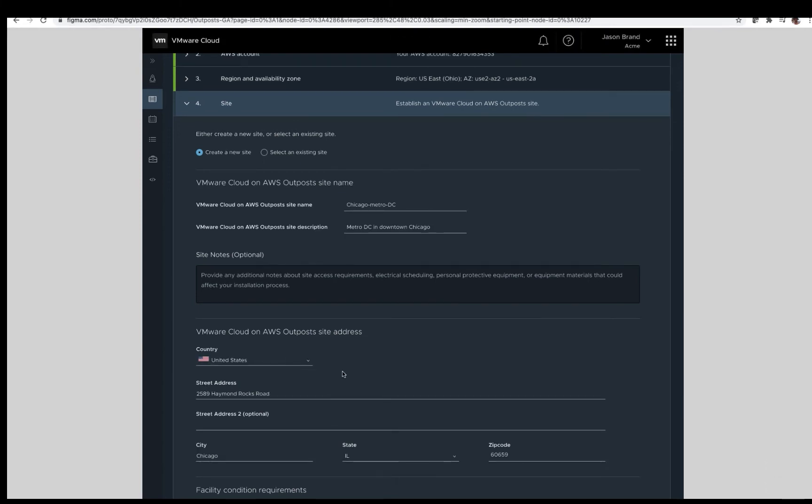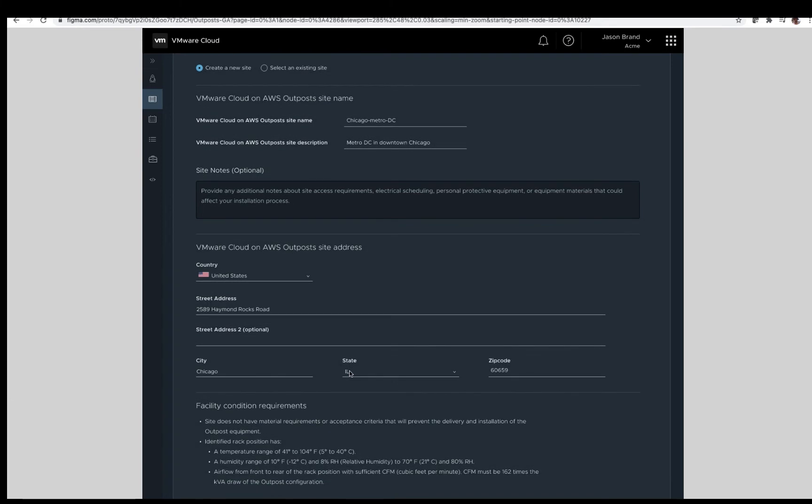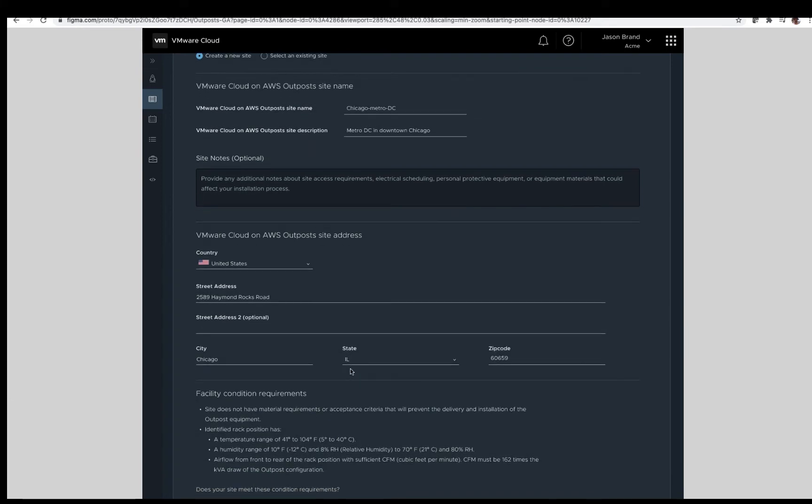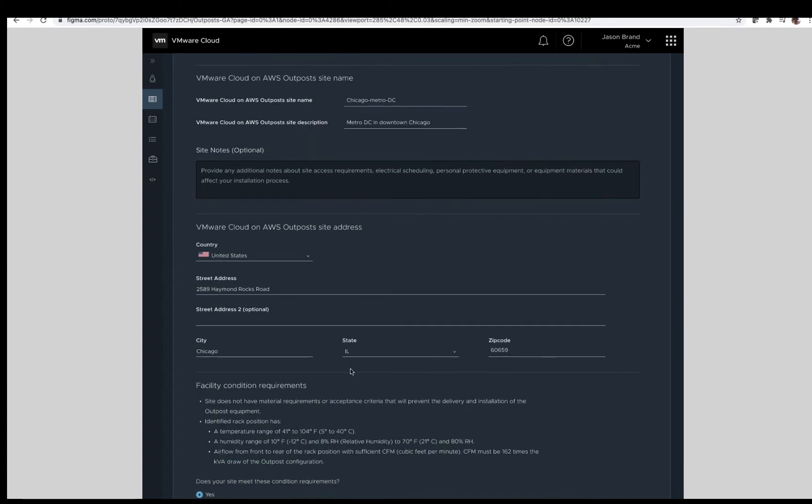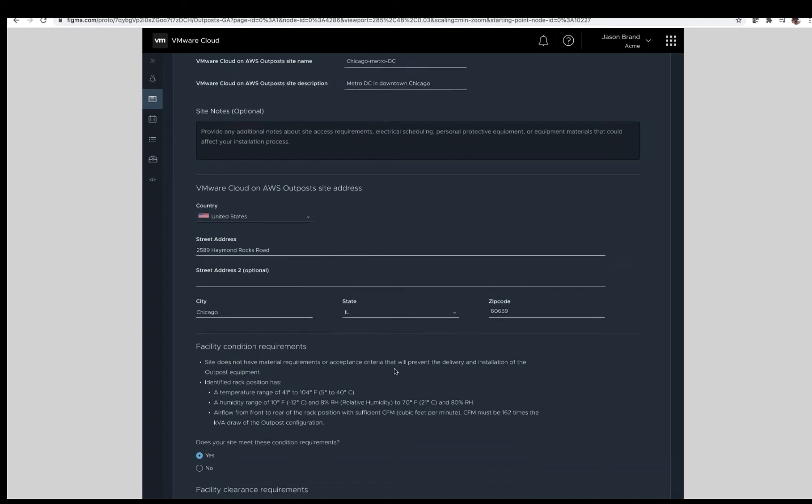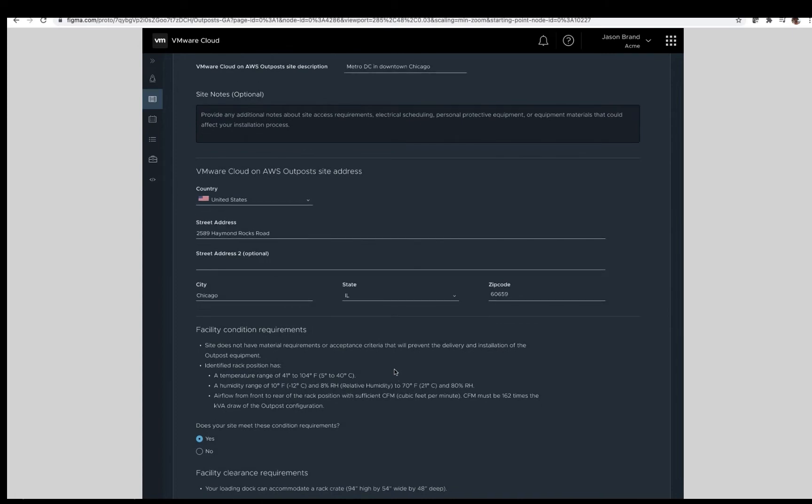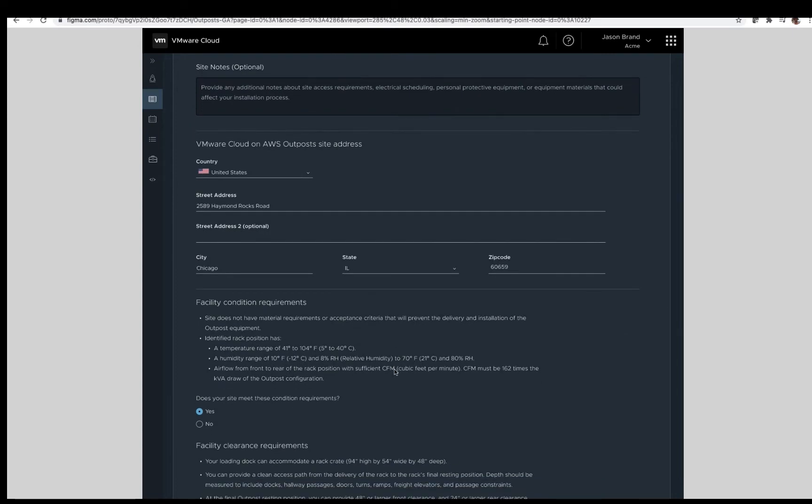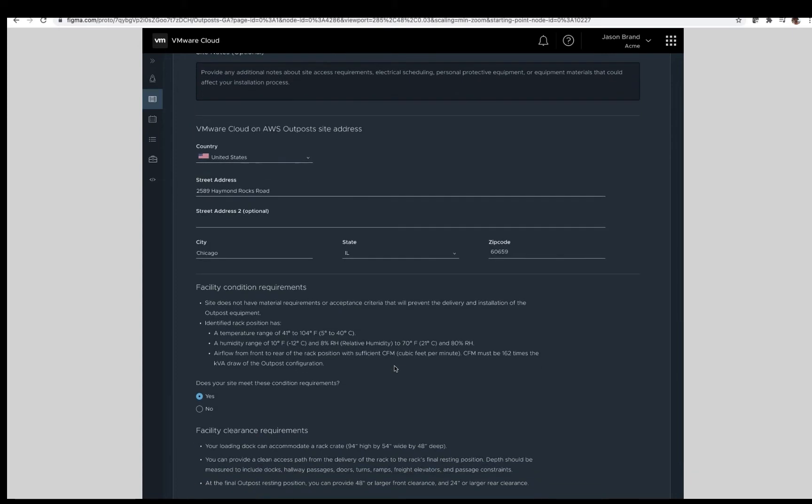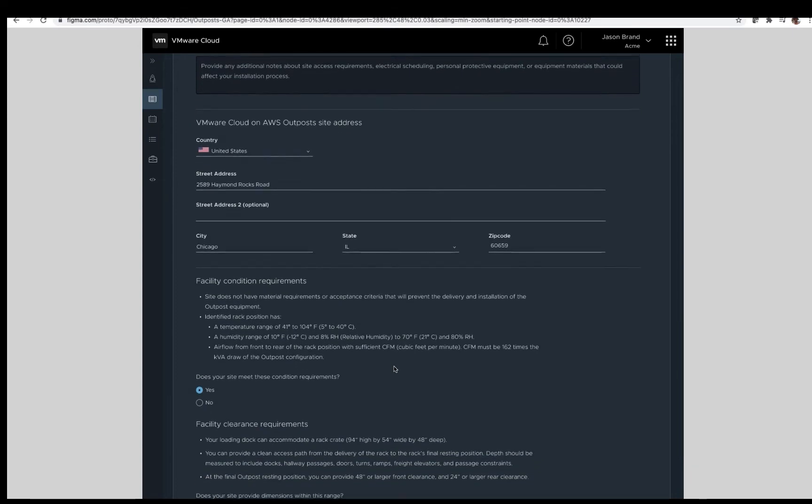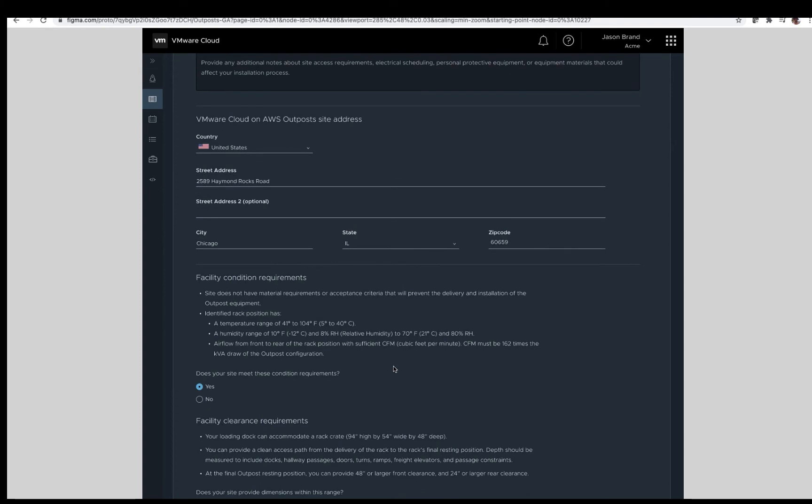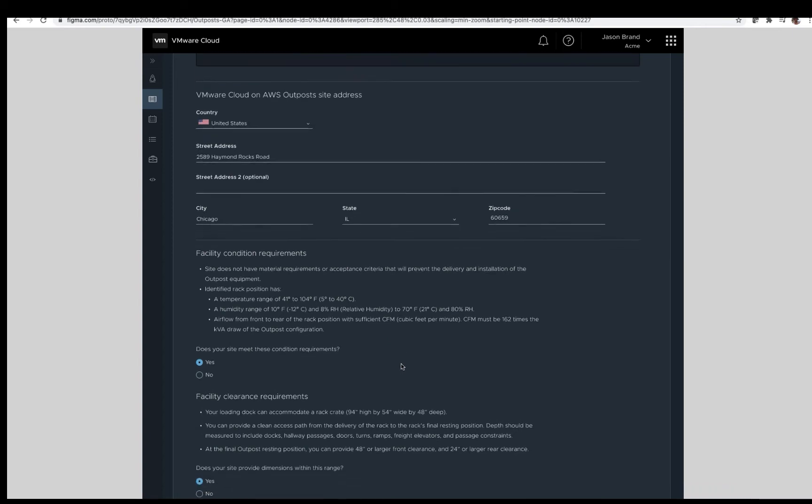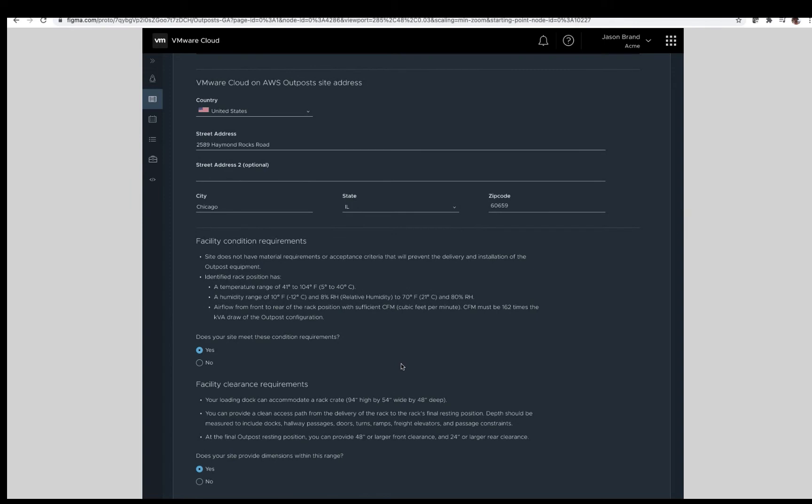Next are the facility condition requirements. Does your site meet the requirements as shown here? The specific temperature and humidity range and air flow requirements. If so, select yes and continue. Facility clearance requirements. Loading dock accommodation of 94 inches high, 54 inches wide, and 48 inches deep, with the ability to provide a clear access path to the rack's final rack position. If your site does meet these requirements, select yes and continue.